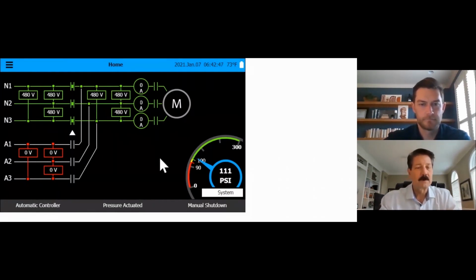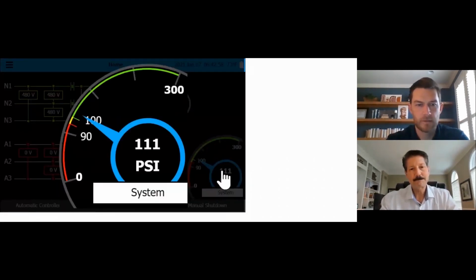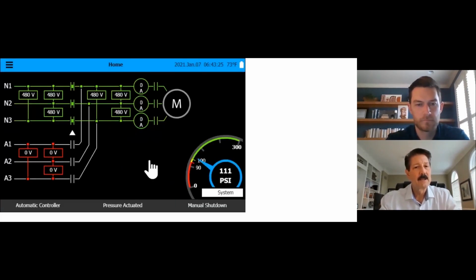As we progress from what we call the home page, as you see in the top center there, we see to the bottom right side some pressure readings. And I'm going to click on this just to enlarge it a little bit. So again, the red would be cut off. So right now we currently have a 90 psi turn on pressure, the cut in. And in this particular case, the cutout is 100 psi. And the system pressure here in the blue circle in the middle is 111 psi for the system itself.